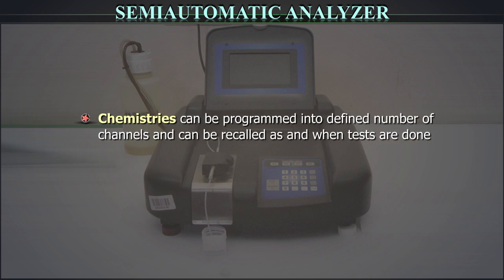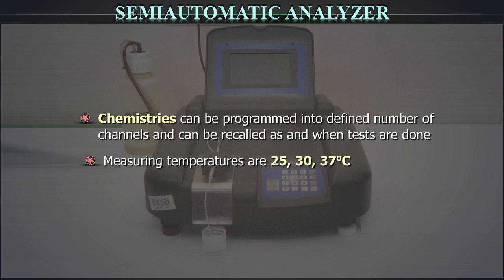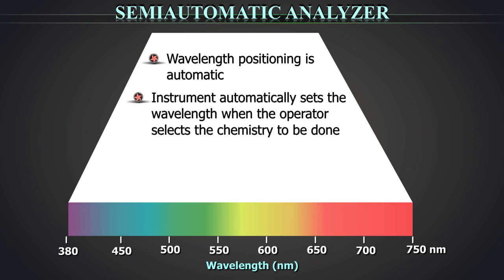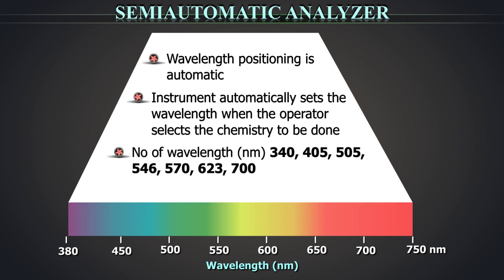Chemistries can be programmed into a defined number of channels and can be recalled as and when tests are done. Measuring temperatures are 25, 30, and 37 degrees Celsius. Wavelength positioning is automatic once programmed. The instrument automatically sets the wavelength when the operator selects the chemistry to be done. Number of wavelengths usually are 340, 405, 505, 546, 570, 623, and 700 nanometers.